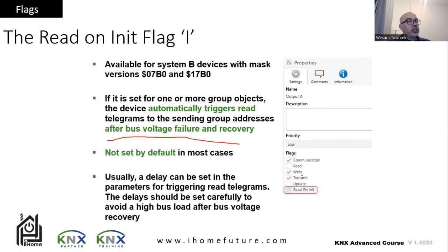By default, it's not on. We normally don't turn it on, because if you put all devices on, it will cause a lot of traffic during the startup of the devices. Most devices will have a parameter in the device itself that lets you put some kind of delay on starting. In this case, I tell the device to put some delay at the beginning of the startup automatically. So normally I don't play with it, and this is the reason we have the I flag.